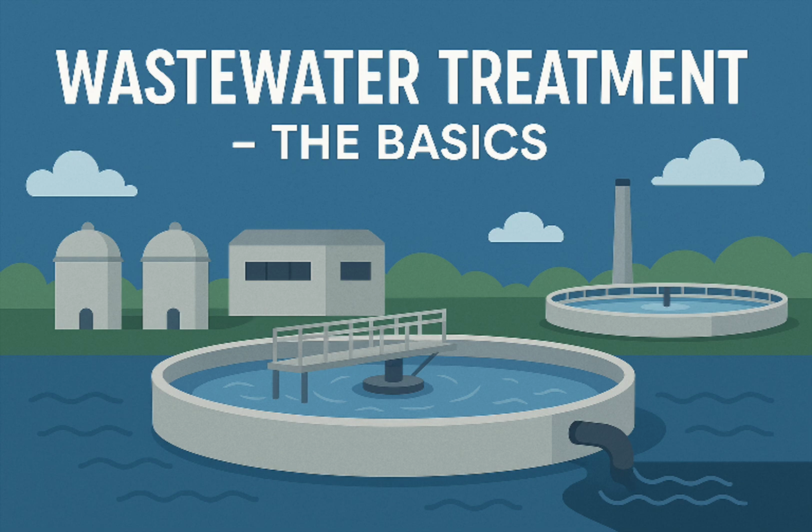How effective is BNR? Very effective. It can remove over 90% of phosphates, for example, much more than conventional secondary treatment, but it takes time. Wastewater might spend, say, 9 hours or so passing through the different zones in BNR bioreactors. That really shows the level of engineering involved.